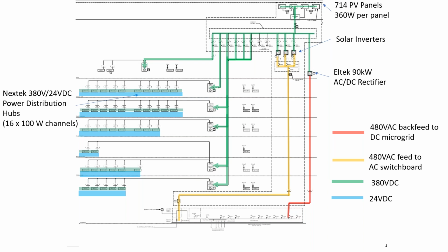During the day, we are going to experience three different scenarios for the PV production. When the PV power generated is larger than the DC load power consumed, the DC bus voltage will rise slightly above 380 volts. And once it reaches a set point, the AC will be backfed to the utility. When the power generated by PV is equal to the DC load, then the voltage will remain constant at the DC bus, and PV will continue feeding the DC load.